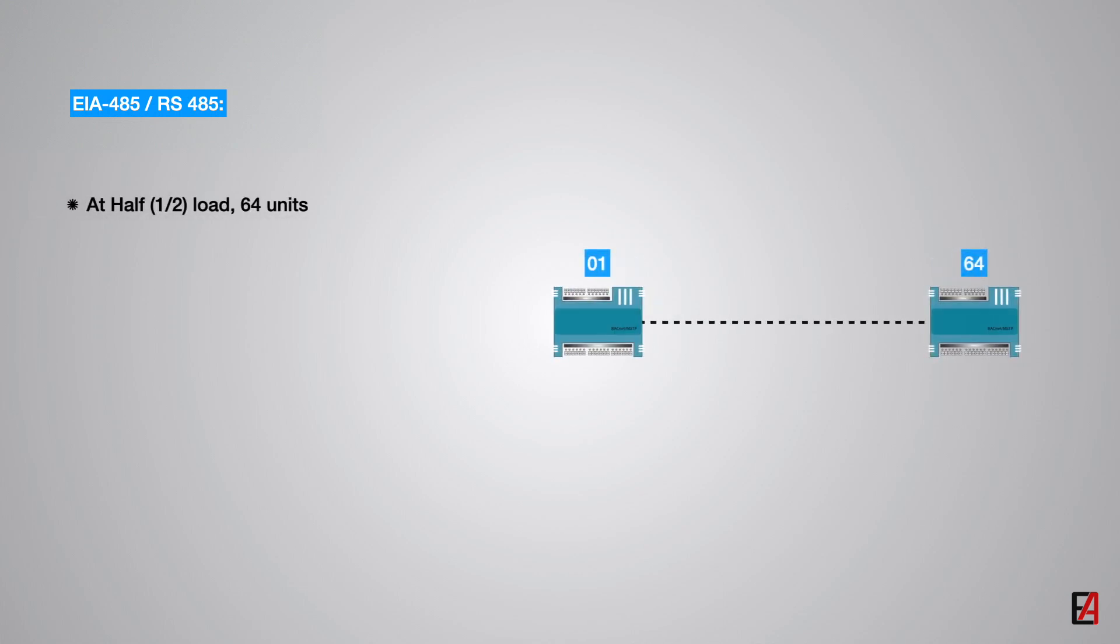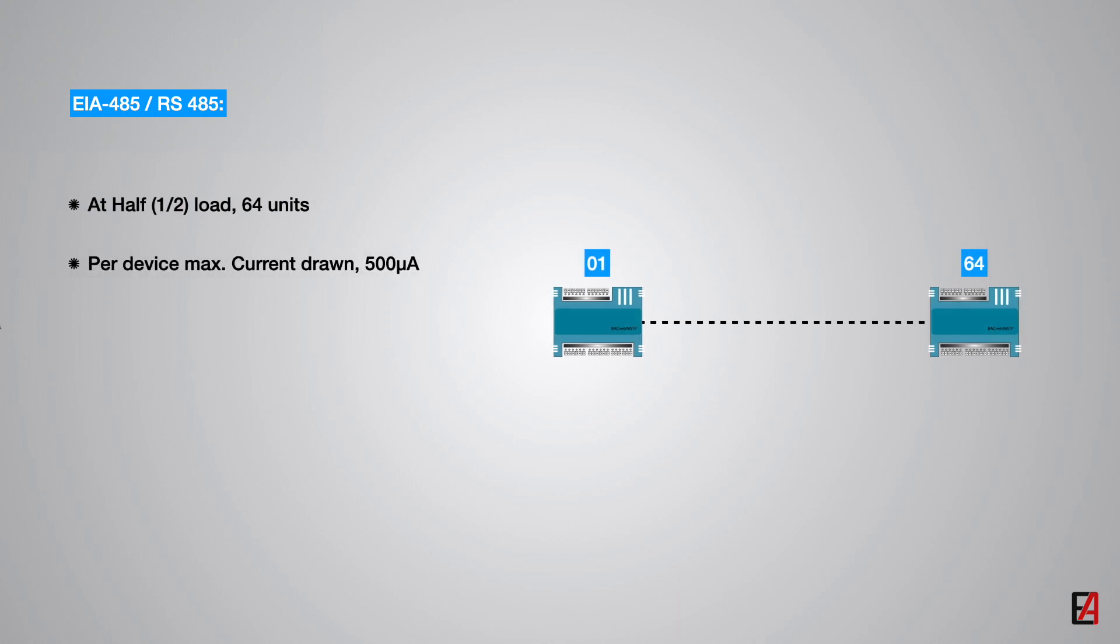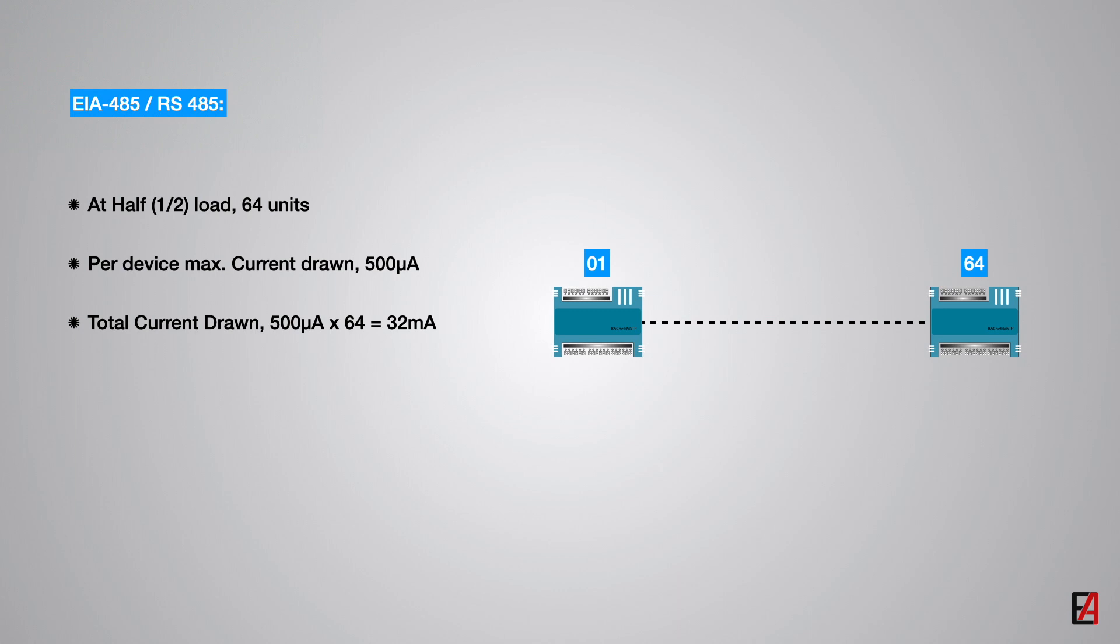With higher input impedance for the RS-485 transceivers, the following reduced load devices are now available. At half load, a maximum of 64 devices can be connected on a single MSTP network, with per device maximum drawing current less than or equal to 500 µA. So the total current drawn on the MSTP network is still complying to the RS-485 standard.